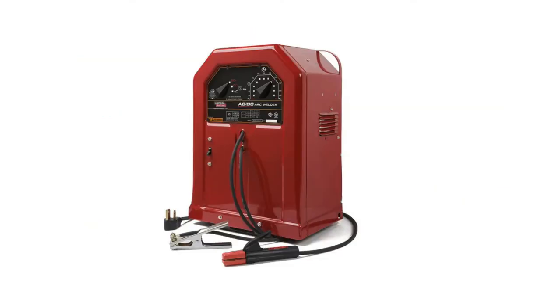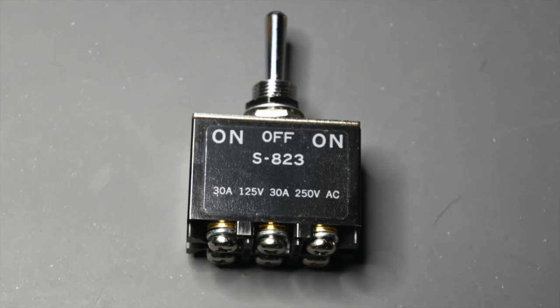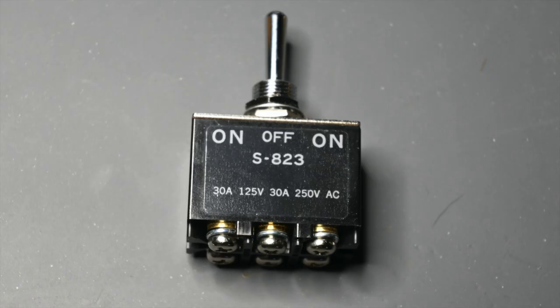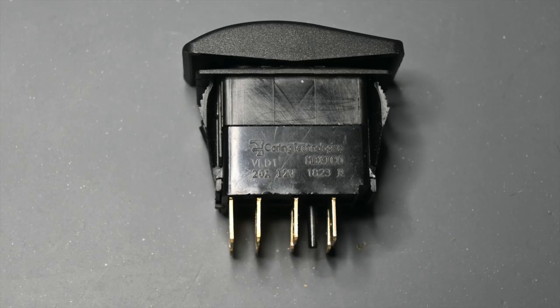Anybody that has ever arc welded with a DC arc welder knows how much more efficient the arc is on DC than on AC. Not all manufacturers mark the voltage ratings on their switches. Do not assume that if the switch only has an AC rating that the DC rating is the same. When the DC rating is not known, always consult the manufacturer's documentation.